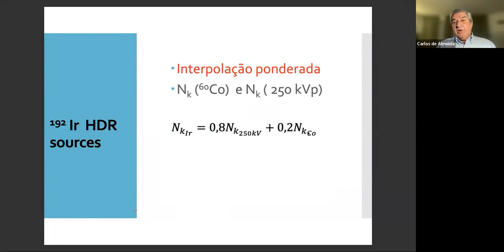That's the way we do it. That's the way the IAEA has recommended. But the Americans are the only country that use a cesium source, cesium and 250 keV. And the problem is that very, very few labs have old cesium teletherapy sources. So in order to be independent of the American philosophy of having to send the chambers to the United States, you can use the NK cobalt at 250 keV, and you are doing very well with that. A comparison has been done. It's published in Medical Physics, and the results are very much comparable. Next slide.